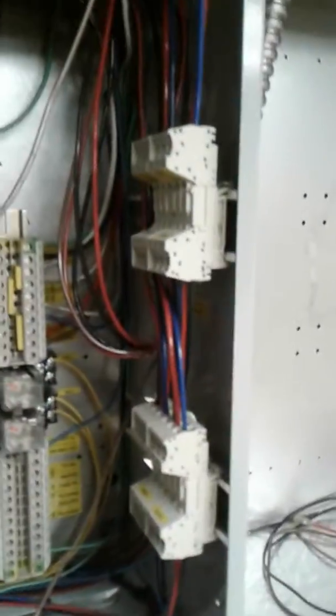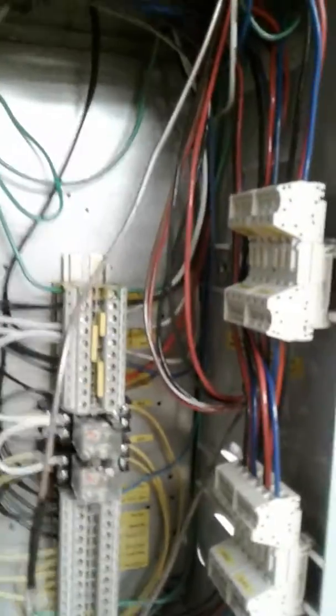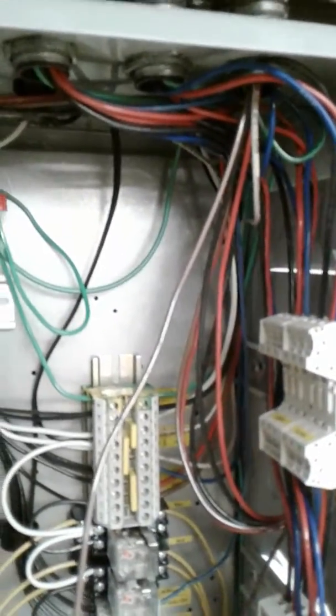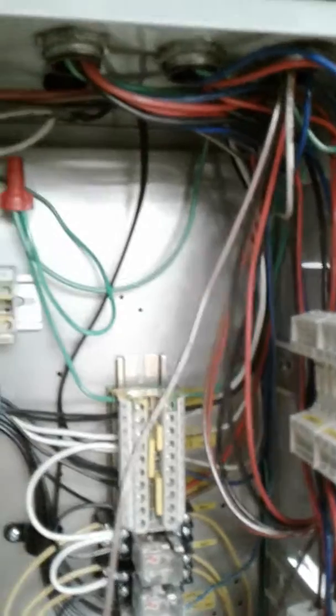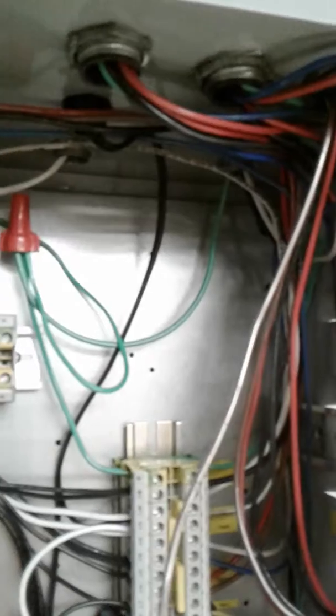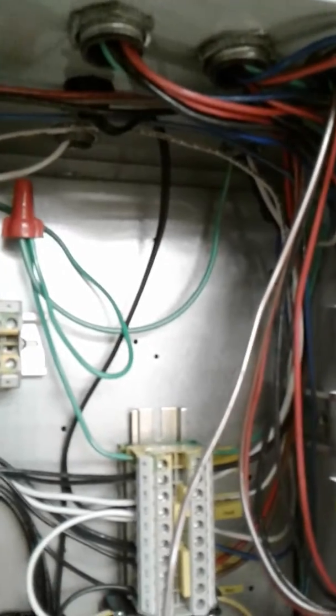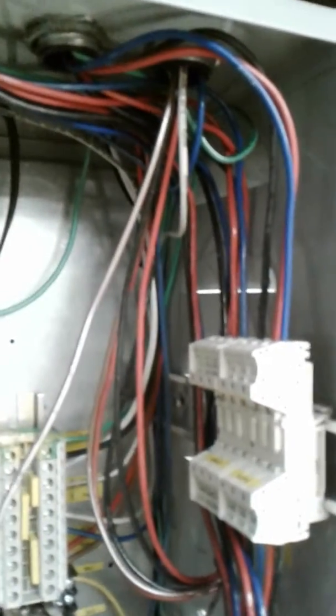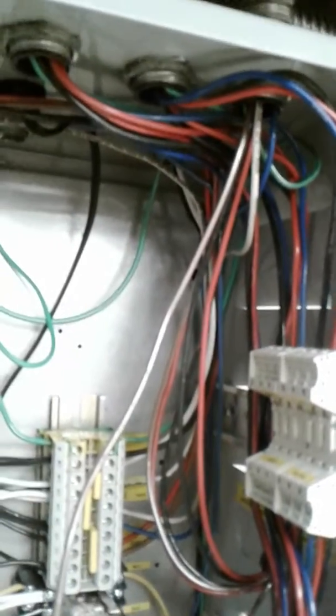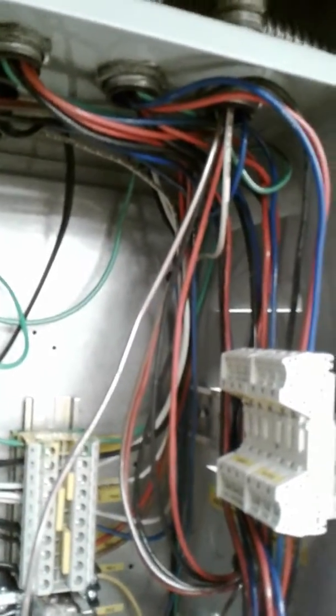So, anyways, it's pretty simple. You just bring your line side into here. Now, this is another thing we ran into. We were told that you have to bring your lines and your loads through separate conduits. We ran ours through the same conduits. And they said, well, it should be fine. Probably won't be a problem. If there is a problem, just run another flex down and run it up through another conduit.